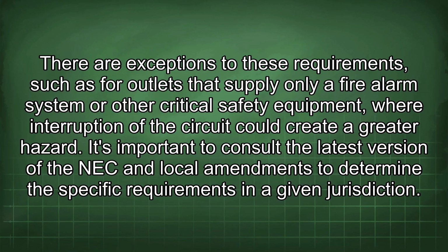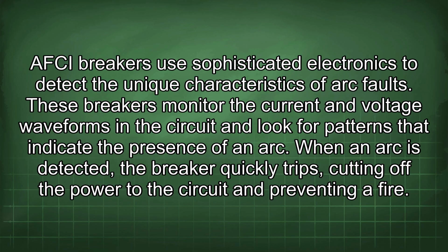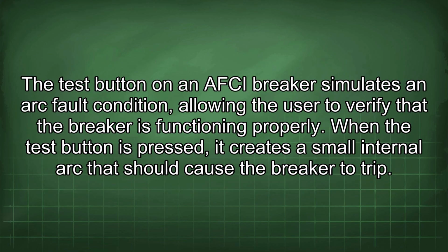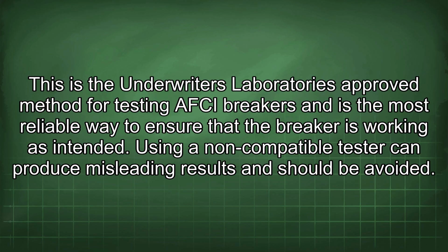to determine the specific requirements in a given jurisdiction. AFCI breakers use sophisticated electronics to detect the unique characteristics of arc faults. These breakers monitor the current and voltage waveforms in the circuit and look for patterns that indicate the presence of an arc. When an arc is detected, the breaker quickly trips, cutting off the power to the circuit and preventing a fire. The test button on an AFCI breaker simulates an arc fault condition, allowing the user to verify that the breaker is functioning properly. When the test button is pressed, it creates a small internal arc that should cause the breaker to trip. This is the Underwriters Laboratories approved method for testing AFCI breakers and is the most reliable way to ensure that the breaker is working as intended.